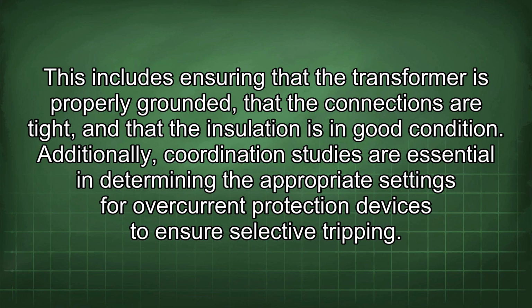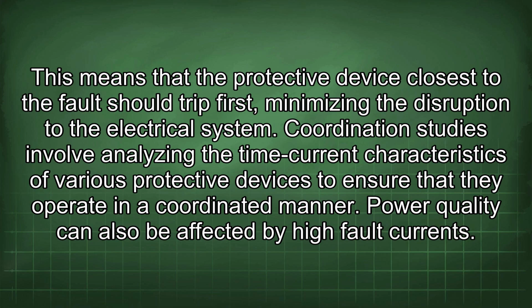This includes ensuring that the transformer is properly grounded, that the connections are tight, and that the insulation is in good condition. Additionally, coordination studies are essential in determining the appropriate settings for overcurrent protection devices to ensure selective tripping. This means that the protective device closest to the fault should trip first, minimizing the disruption to the electrical system. Coordination studies involve analyzing the time current characteristics of various protective devices to ensure that they operate in a coordinated manner.